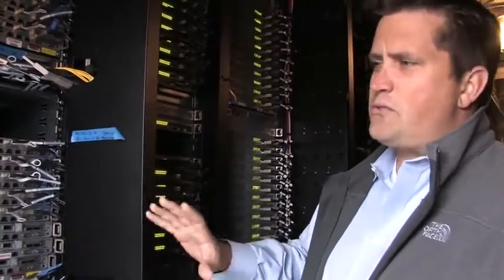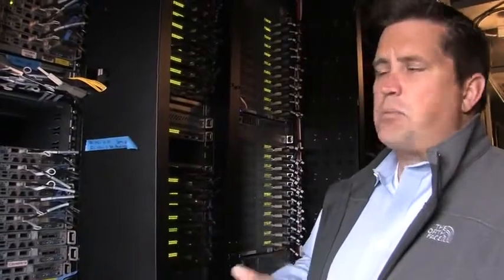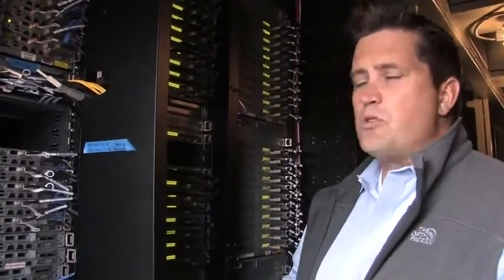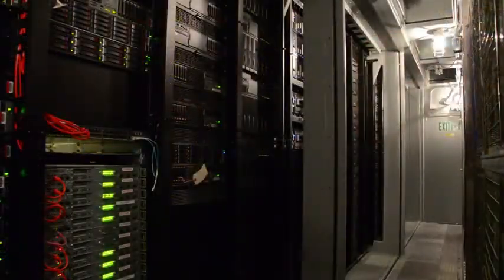data center. What that allows us to do is remove fans from the systems themselves. So in each of these racks there are no fans in the servers. The only fans that are present are in any networking gear that would require them. What that allows us to do is remove that burden from each server and apply it to more IT in our module. So effectively what we're doing is making our modules more power dense and removing elements that decrease efficiency. So by not having fans at the small scale, we are utilizing fans at the large scale, or in our air handler.